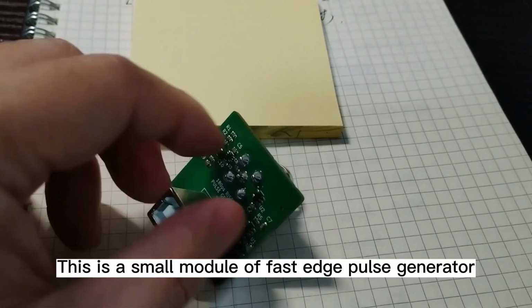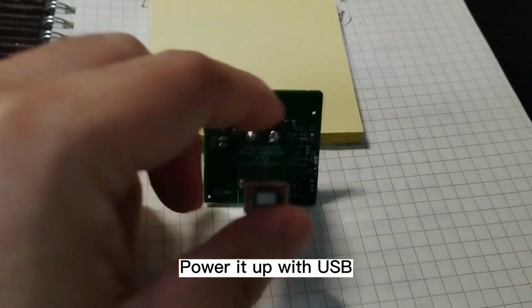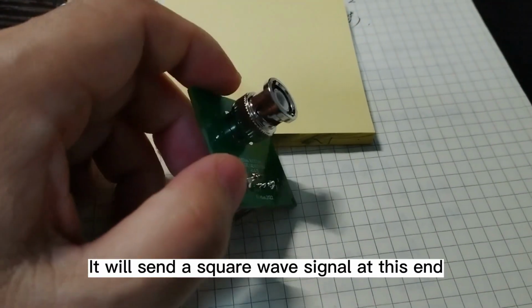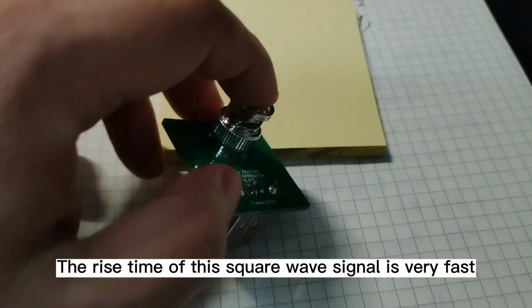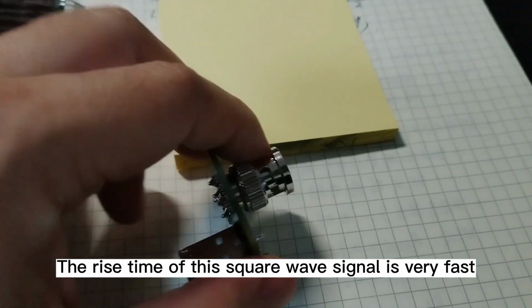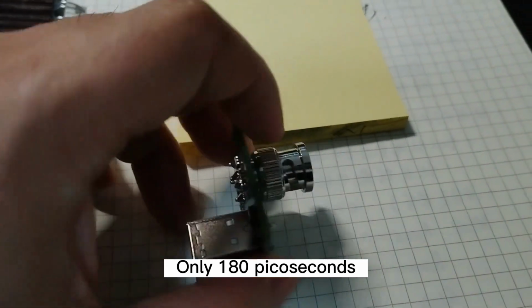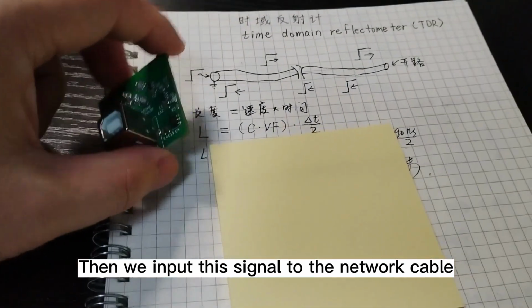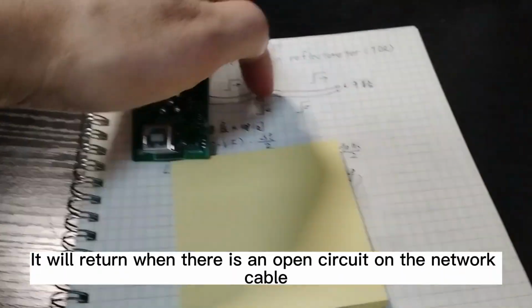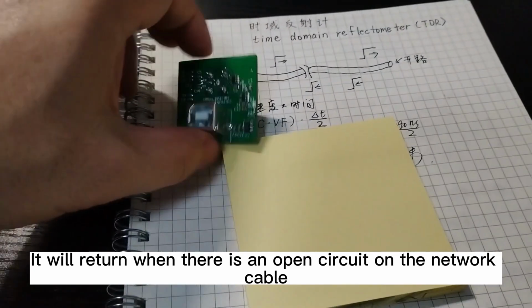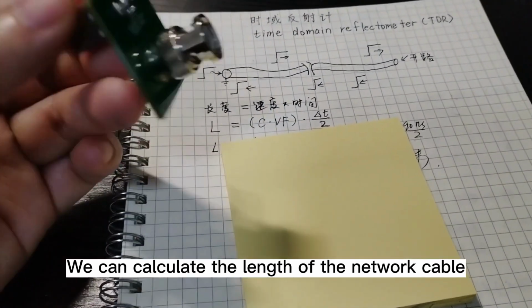This is a small fast edge pulse generator module. Power it up with USB. It will send a square wave signal at this end. The rise time of this square wave signal is very fast, only 180 picoseconds. Then we input this signal to the network cable. It will return when there is an open circuit on the network cable. We can calculate the length of the network cable.